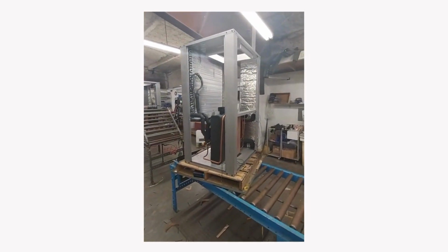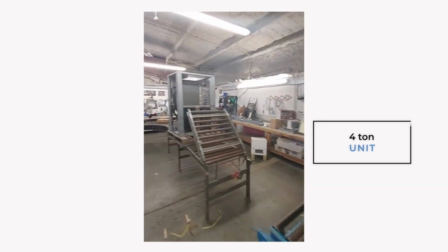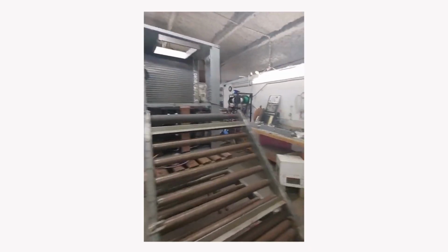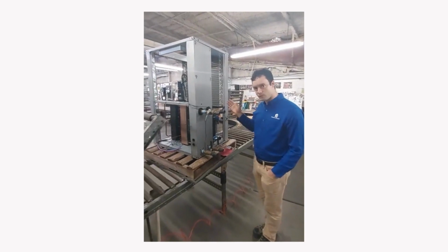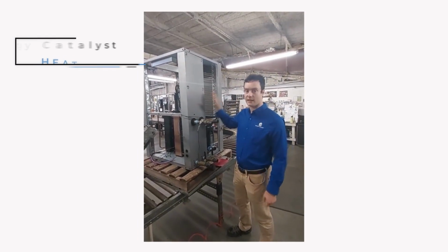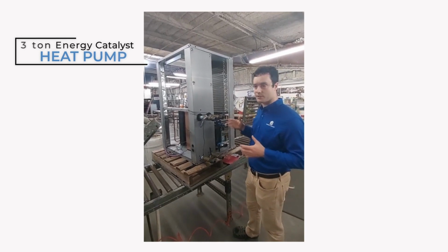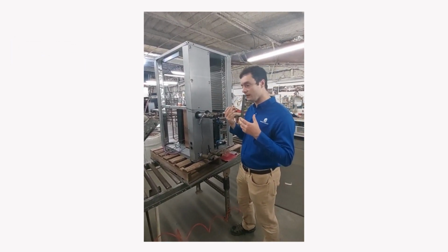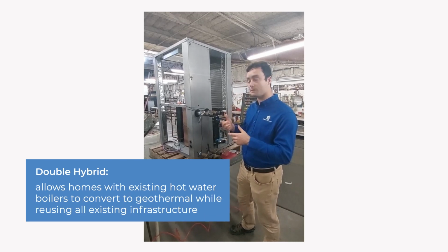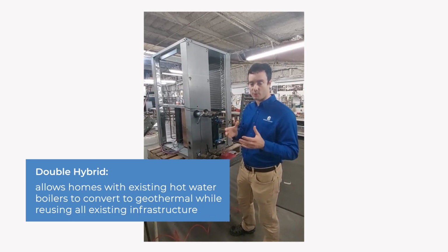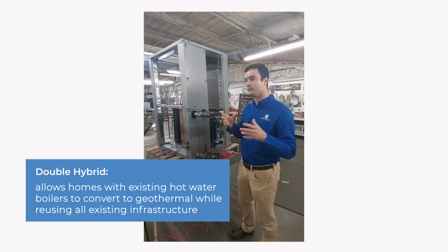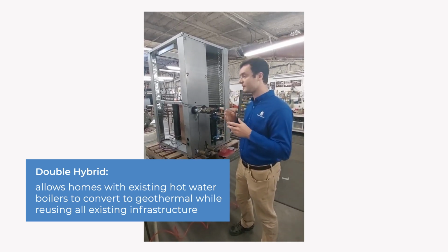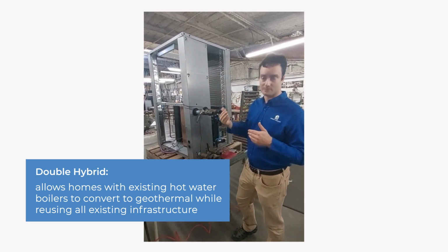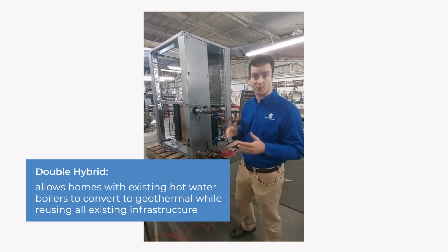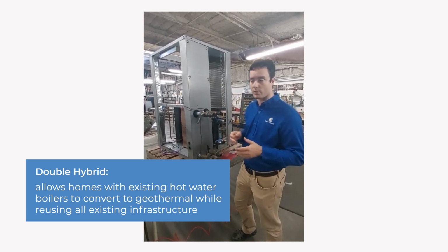And right over here, we have 2 units that are pretty close to finished. This is a 4-ton unit over here, and then a 3-ton down the line. Let's just talk about this one for a minute. What we're looking at here is a 3-ton Energy Catalyst heat pump. This is a double hybrid, so it can operate in a hot water heating mode and provide supplemental hot air to make sure that the home, even if you have baseboards or radiators, still can be heated properly. It can always get the full capacity of the unit, even if there are some limitations with relatively low temperature hot water running through baseboard or radiator.